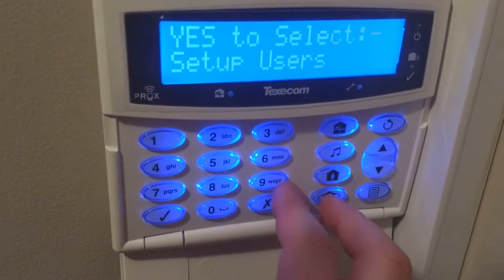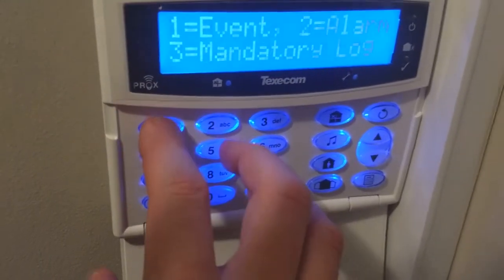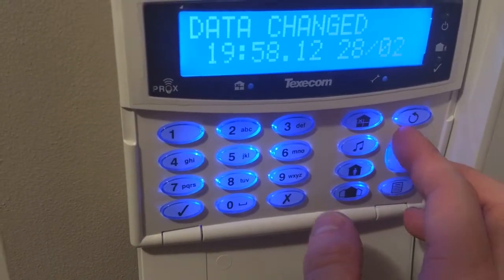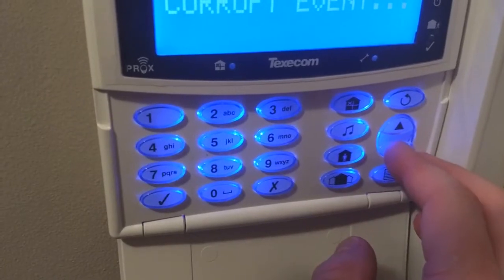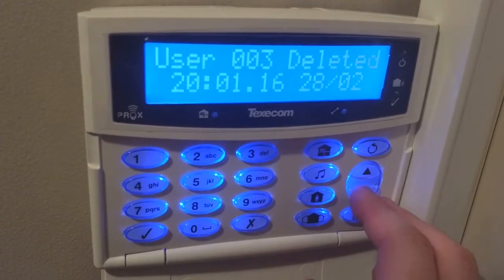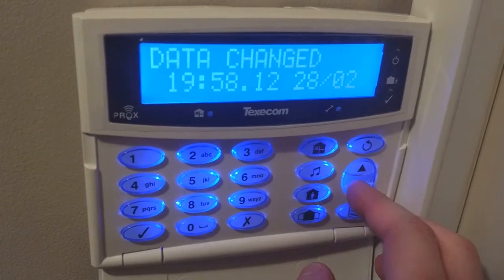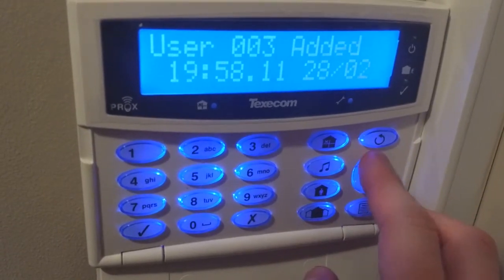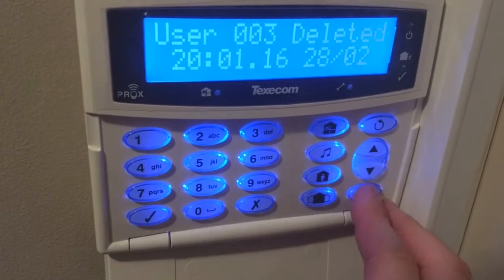If I was then to go into the event log, it would show that I've deleted the user. If you press up it will take you to the first event created, but that's during the panel's boot up, which is why you've got a corrupt event. If you press down, you go backwards through time — so you can see that the user is deleted, I've changed some data, and I've added the user: that's when I added it, that's when I changed the data, and that's when I deleted that user.